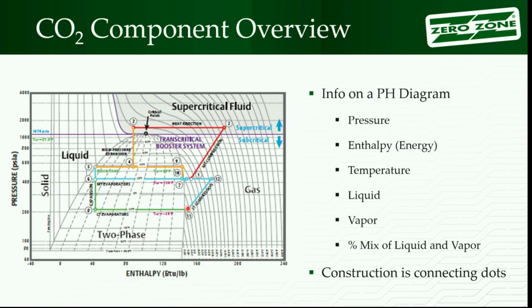You look at the software, it tells you what the discharge temperature is going to be. I can find that discharge temperature line. I drop a point. Suction to discharge, I draw a line. Same thing when I move back into the, that discharge gas is going to go back to the compressor. It's going to get cooled off somehow, moves to the left. And how much cooling it is will decide where you put that point. And so you can go through and drop those points. Main thing we want to stay focused on is that the condenser is going to be a horizontal line. We're assuming no pressure drop.